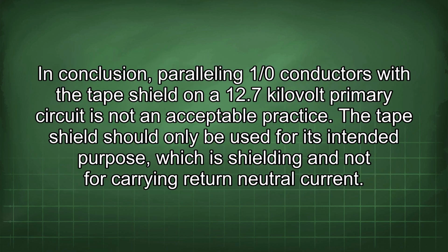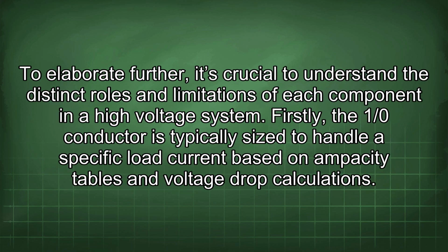In conclusion, paralleling 1/0 conductors with the tape shield on a 12.7 kilovolt primary circuit is not an acceptable practice. The tape shield should only be used for its intended purpose, which is shielding and not for carrying return neutral current. To elaborate further, it's crucial to understand the distinct roles and limitations of each component in a high-voltage system.